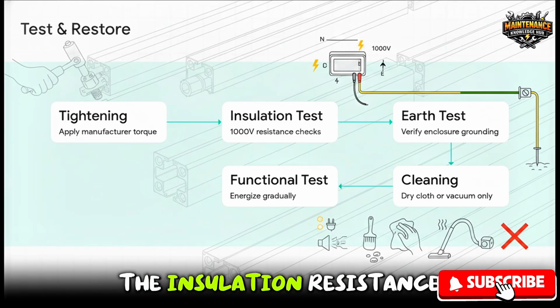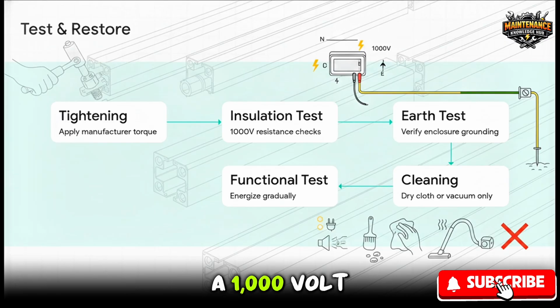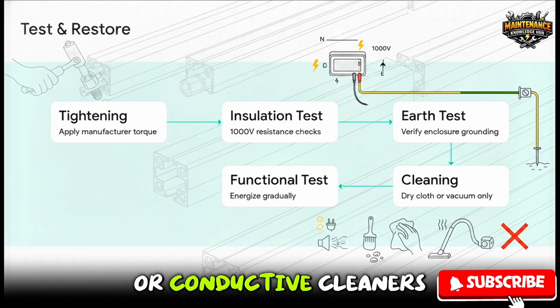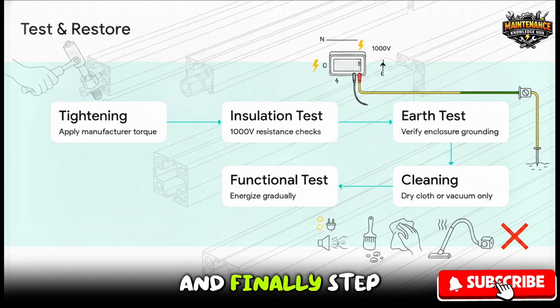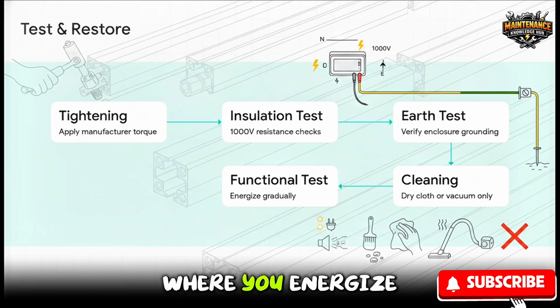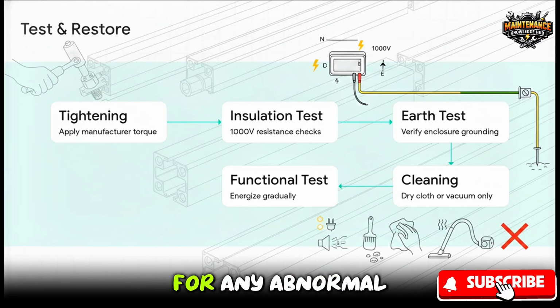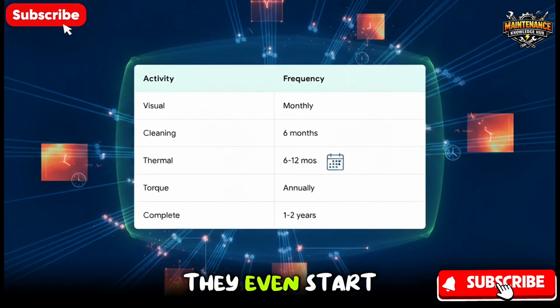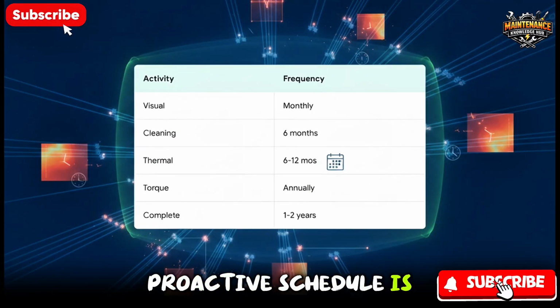Step 2 is the insulation resistance test, usually done with a 1000-volt tester checking phase to neutral, and phase to earth. Step 3 ensures the system is safely grounded via an earth continuity test. Step 4 is cleaning. You must only use a dry, lint-free cloth, a vacuum, or a non-conductive brush. Absolutely no water or conductive cleaners whatsoever. And finally, step 5 is the functional test, where you energize the system gradually and monitor closely for any abnormal noise, smells, or vibrations.